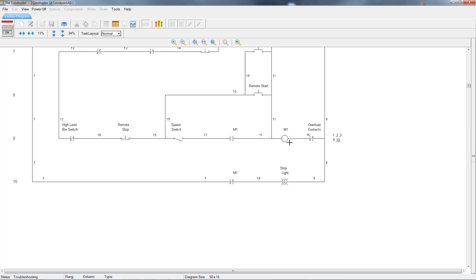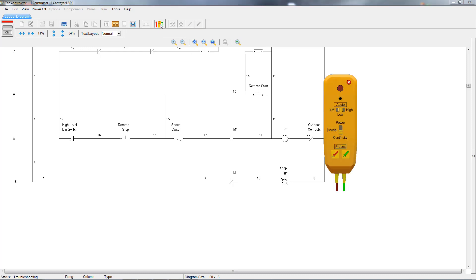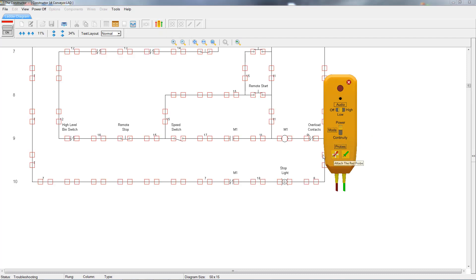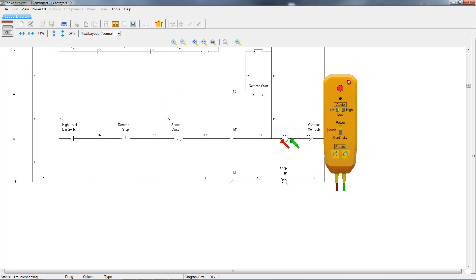But with a test probe, we can test for power on the coil. We'll set the mode back to power and then connect the probes to the connecting wires of the coil. Right now we can see that there is power on the coil. Let's go ahead and push the stop button down, and now we can see that there isn't any power on the coil.